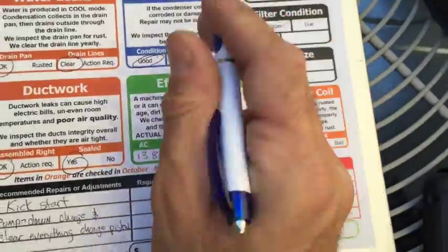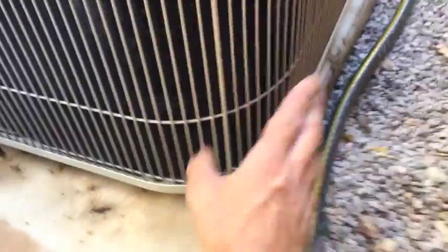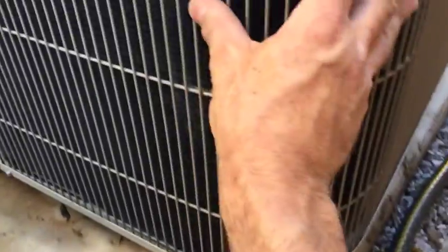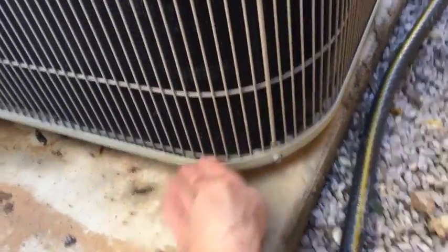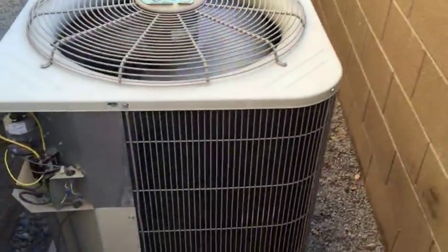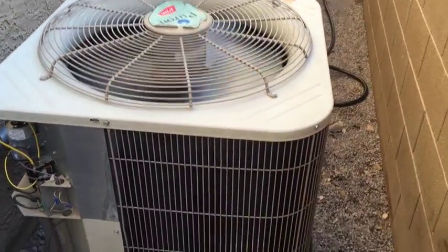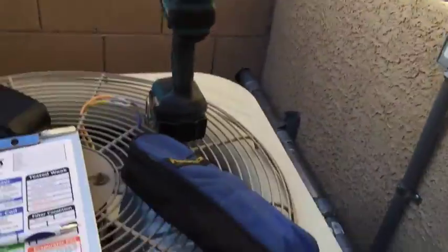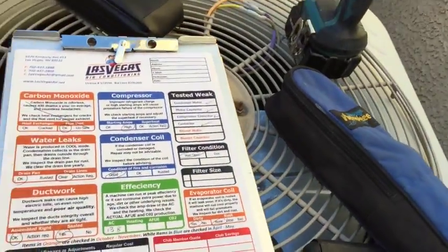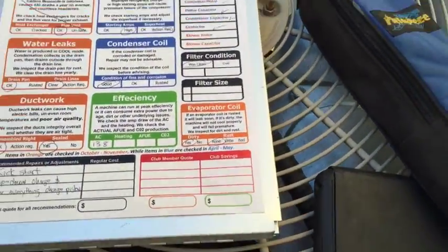So now, that thing you saw us do when we took this apart was very important, very vital. These machines here will last forever if you keep these rocks out of the inside there. Because what these types of machines do is the rocks get in there, and then this vibration you can hear rubs on that rock and you get leaks. And that's where the condenser coil leaks come from, in these types of systems. Notorious for that. So anyway, that was a check and tune, and that's how we do it.